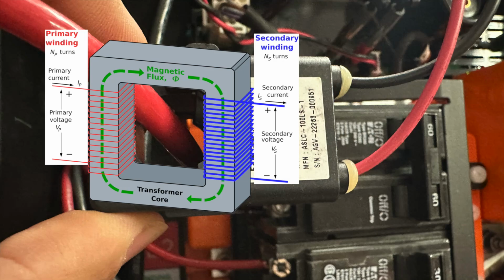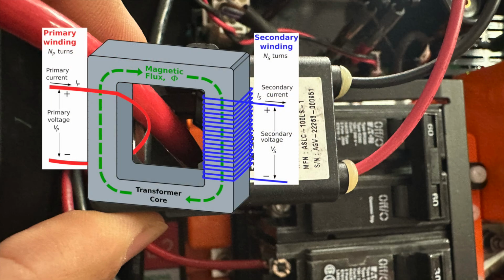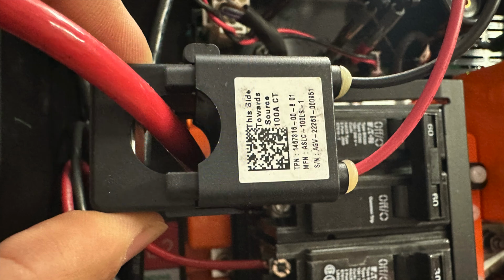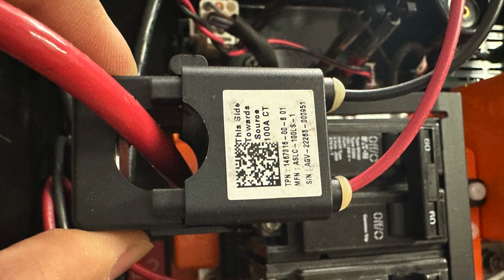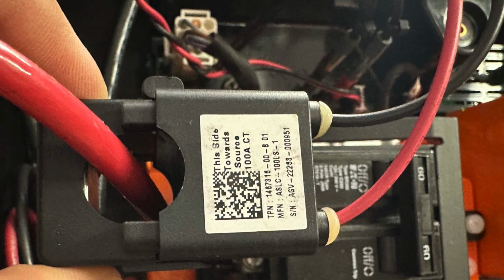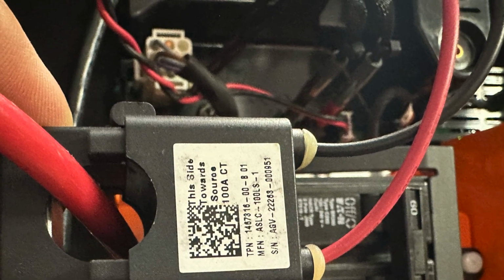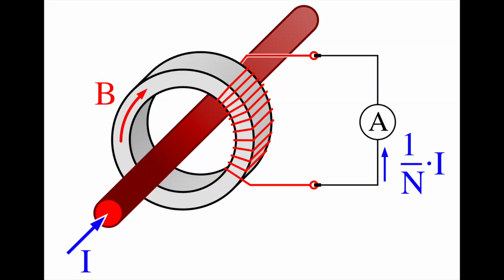And CTs are designed to just clip around a wire, so they actually contain only the secondary winding. The primary winding of a CT is literally just the wire that you're clipping it around. That wire becomes the single-turn primary winding. Genius. Alright, so a CT, when used in a metering system, is basically the first half of an ammeter, and the two wires coming out of it contain the transformed current that will actually be measured directly. That understanding should help us get our bearings when we open everything up.